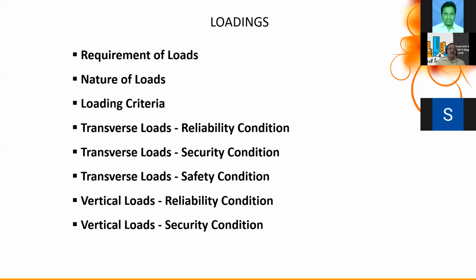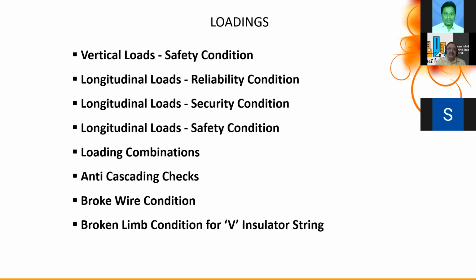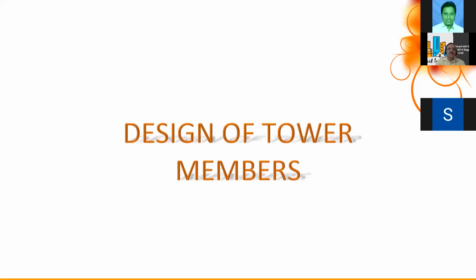Loadings, we consider, one design of one transmission tower will have up to 180 loading conditions, loading combinations. We have the nature of loads: dead loads, live loads, working loads, that means maintenance loads, and we have minimum temperature, maximum temperature, wind, and loads in the direction of transverse, longitudinal, and vertical, XYZ. So security condition, reliability condition, and safety condition. So these are all the conditions we design these transmission towers for.